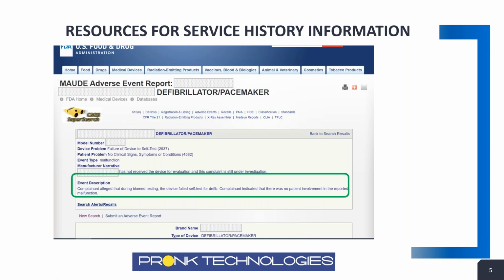And what's also helpful is that under event description, it will give you an overview of what the issue was. In this particular case, you could see here that the biomed was doing some testing and it failed to self-test for the defib. They also indicated there was no patient involved, but they felt it was important to report it to the FDA, and they did so. And so it gives you really good information below that.